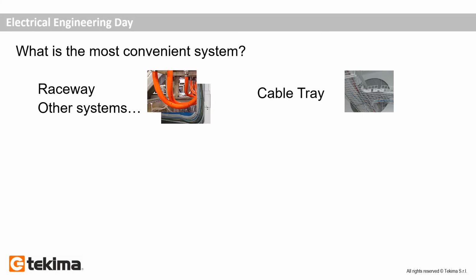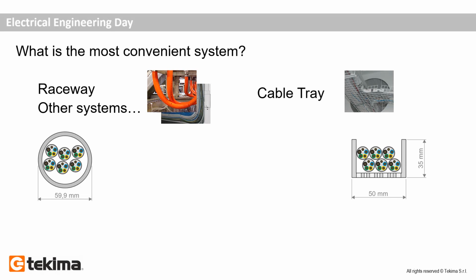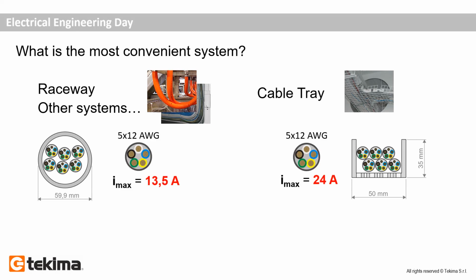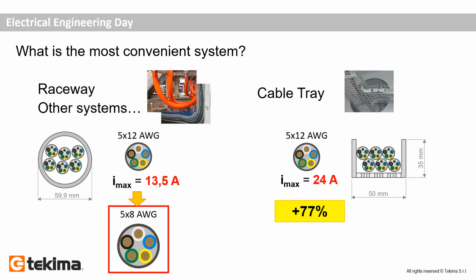So if we go back to the original question, what is the most convenient system, raceway or cable tray? The answer is related to the maximum performance that the systems allow to obtain with the cable. For the raceway, we can reach up to 13.5 amperes. With the cable tray, we can reach up to 24 amperes, so it's 77% more ampacity with respect to the raceway. If we want to reach the same operating ampacity in a raceway, we should move from a 5 conductors 12 AWG size to a 5 conductors 8 AWG size, which means that we have to size again the raceway, moving from a 2-inch to a bigger diameter.